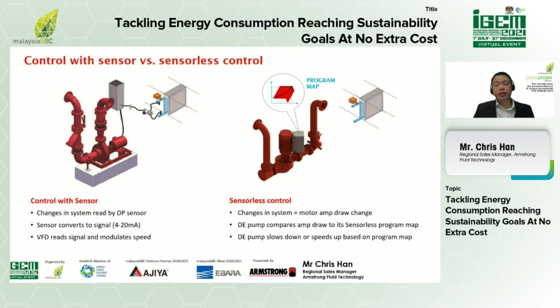The pump control then automatically adjusts the speed and ramps up or down according to the needs of the system, always looking for that constant feedback to adjust itself to the system conditions. Again, ensuring that as little energy as possible is used, delivering what the building needs. So this response is not only quick, but also more accurate, while saving energy and reducing greenhouse gases.